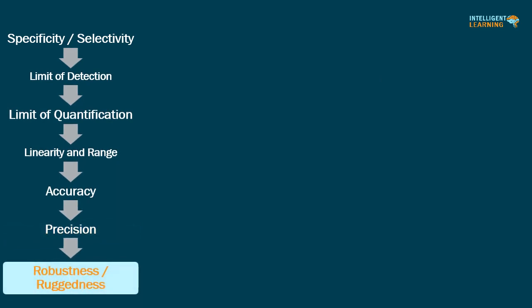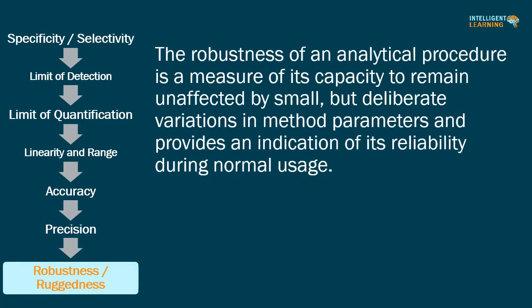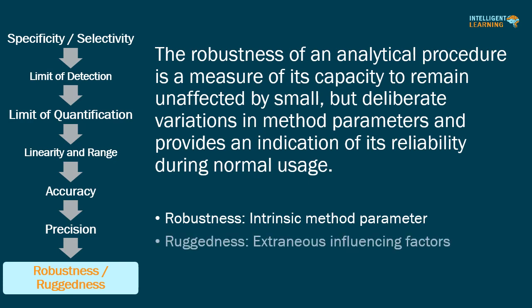The robustness of an analytical procedure is a measure of its capacity to remain unaffected by small but deliberate variations in method parameters, and provides an indication of its reliability during normal usage. Robustness expresses the stability of the method against small variations of intrinsic method parameters and variability of sample matrix. Ruggedness expresses the stability of the method against extraneous influencing factors. Some guidelines use robustness and some use ruggedness; when used together, these terms are treated as synonyms in most cases.